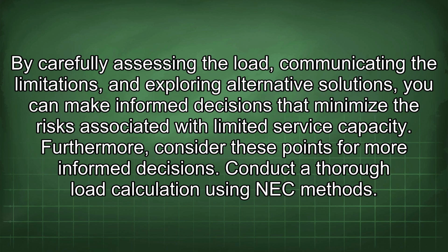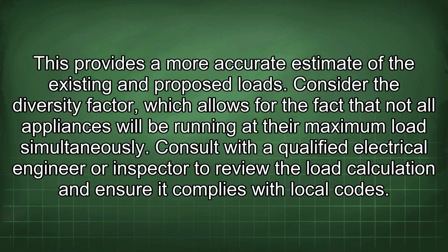Furthermore, consider these points for more informed decisions. Conduct a thorough load calculation using NEC methods. This provides a more accurate estimate of the existing and proposed loads. Consider the diversity factor, which allows for the fact that not all appliances will be running at the maximum load simultaneously. Consult with a qualified electrical engineer or inspector to review the load calculation and ensure it complies with local codes.